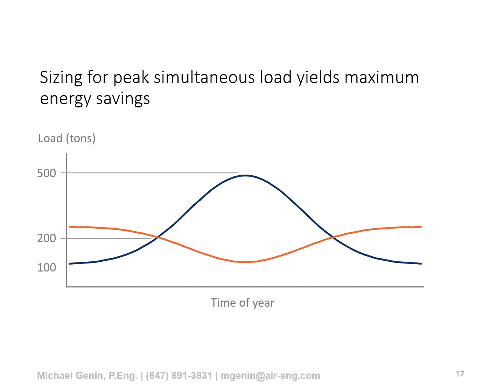you can see I've represented the cooling load with the blue line and the heating load with the red line. In the center of the graph, this would be the summer, and on the edges of the graph would be the winter. So let's assume we have a 500-ton peak cooling load. We have a 100-ton cooling load in winter that represents the cooling load of those core zones. And we have kind of an equilibrium point where heating and cooling loads are roughly equal, and that occurs in the shoulder season at around 200 tons.